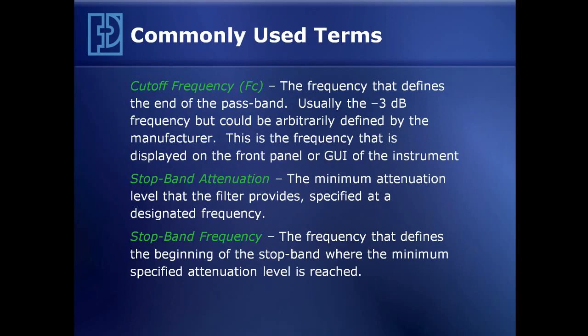Other terms we've already alluded to: the cutoff frequency, designated as F sub C, is the frequency that defines the end of the passband — usually the minus 3 dB frequency, but it can be arbitrarily defined by the manufacturer. This is the frequency displayed on the front panel or GUI software for the instrument.